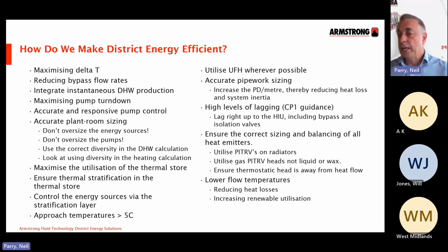Accurate pipework sizing, and I'd suggest moving, certainly on the lateral pipework, away a little bit from the standard 250-300 pascals per meter, and look at increasing that up to, say, 600 pascals per meter. You'll find that you'll still probably be well within the velocity limits outlined in CP1, but the objections to that normally are, well, what about erosion? What about noise? And we have to remember this is a variable volume system where the peak demand occurs for a very small period of time, and it only occurs when there is high domestic hot water demand.